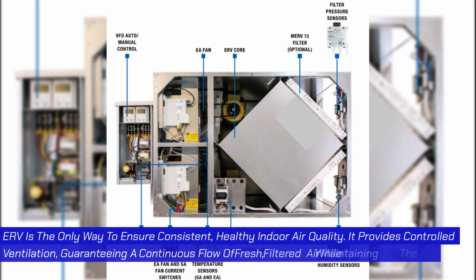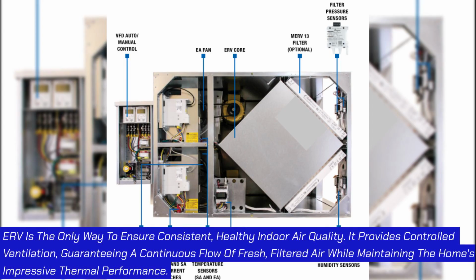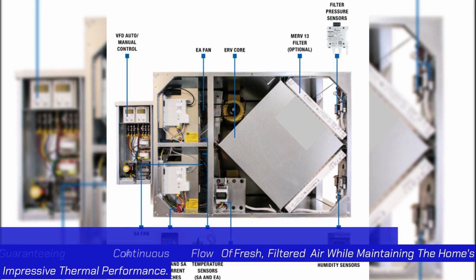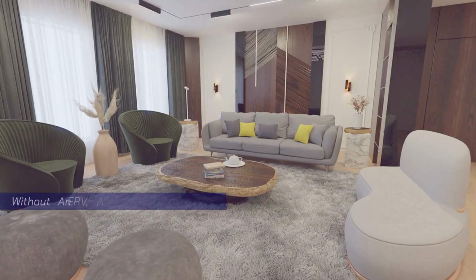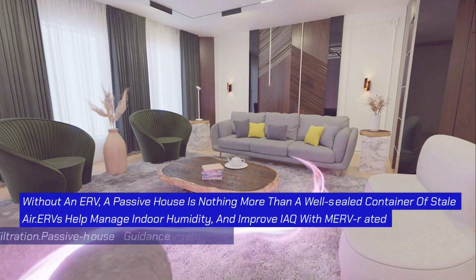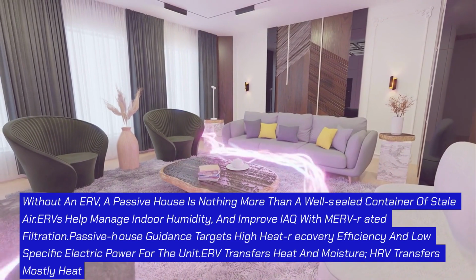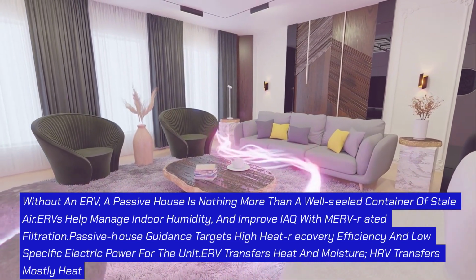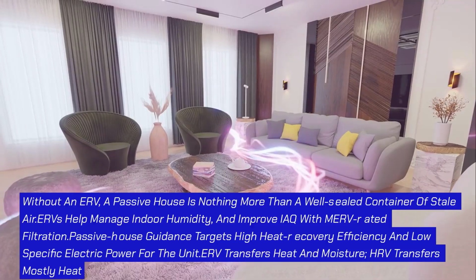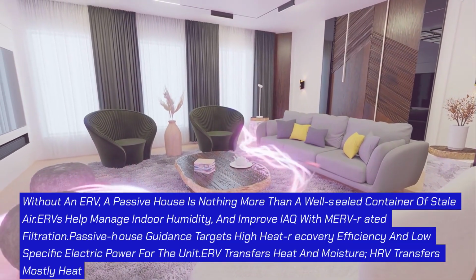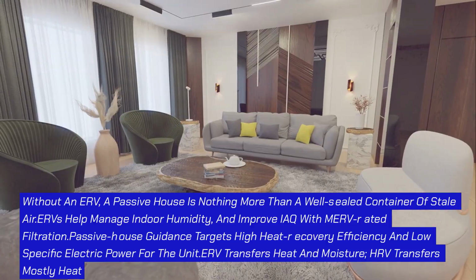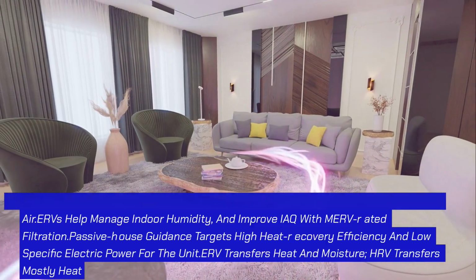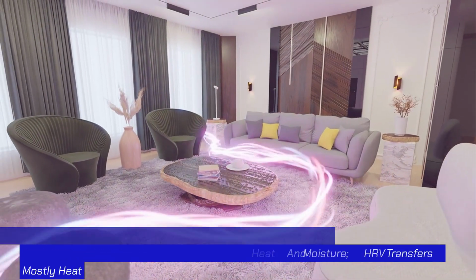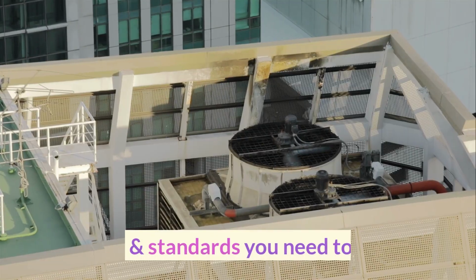ERV is the only way to ensure consistent, healthy indoor air quality. It provides controlled ventilation, guaranteeing a continuous flow of fresh, filtered air while maintaining the home's impressive thermal performance. Without an ERV, a passive house is nothing more than a well-sealed container of stale air. ERVs help manage indoor humidity and improve IAQ with MERV-rated filtration. Passive house guidance targets high heat recovery efficiency and low specific electric power for the unit. ERV transfers heat and moisture. HRV transfers mostly heat.